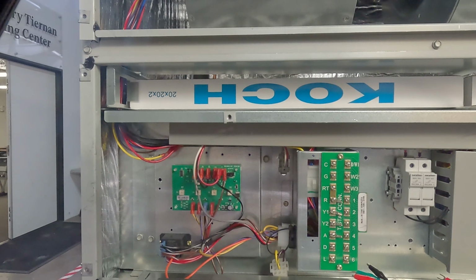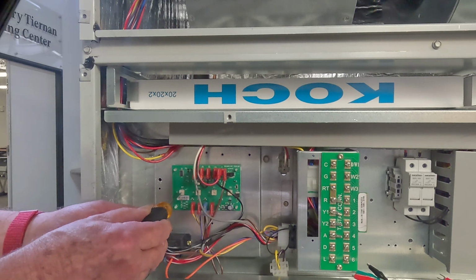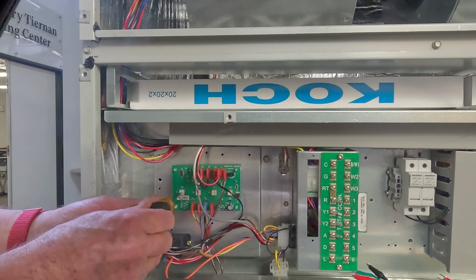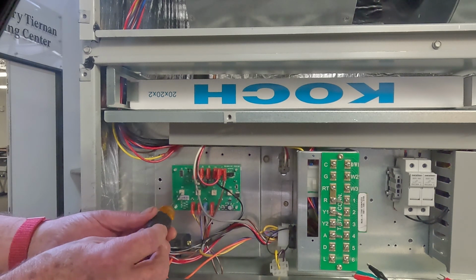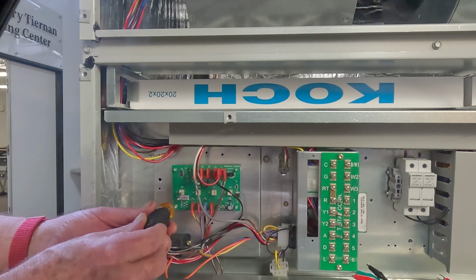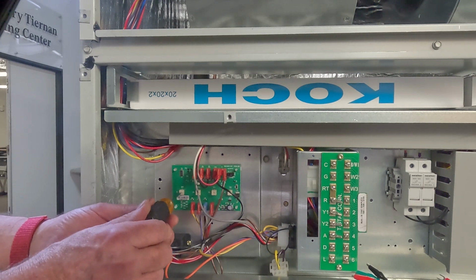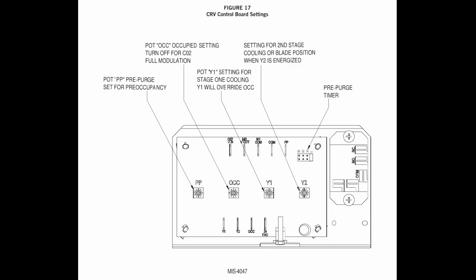All potentiometers are set to a closed damper from Bard. Turning counterclockwise will close the blade. Clockwise will open the blade. The pot switches are fast acting and again very delicate. You will start with the basic non-CO2 sensor controlled method.